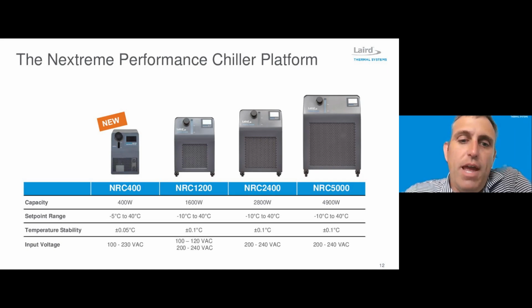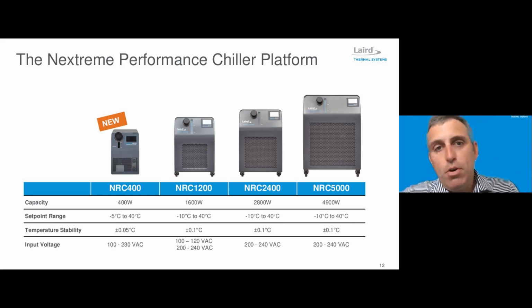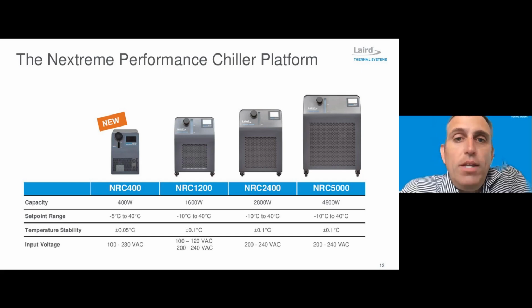So it's a temperature differential. If we're running the system at 0 degrees C differential, meaning the set point of the fluid is the same as the ambient temperature, it's capable of 400 watts. When we want to cool below that ambient temperature, that cooling capacity decreases. So it's related to the refrigerant, but it has a different, definitely more direct impact from the ambient temperature. So from an operating range standpoint, in terms of the ambient conditions, I believe it's more a typical 10 to 40 degrees C ambient, but that ambient temperature is going to directly impact the set point that you're capable of achieving. So I hope I answered that question accurately. If not, please reach out to us. We can follow up.